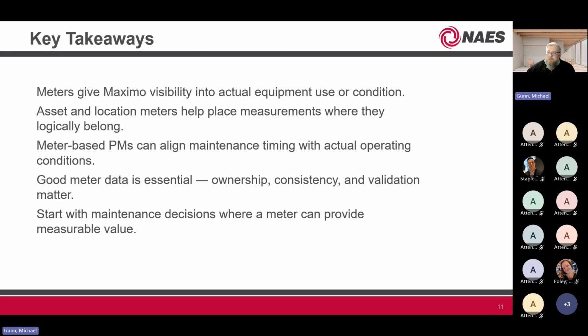Good meter data is essential - that's about ownership, consistency, and training technicians or whoever is taking readings. If it's not automatically integrated, you need to take proper readings and double check and validate the information from time to time. I don't know how many times I got calls when I was a Maximo admin saying our guys messed up this meter reading. They had access to fix it, but we just had to go back and fix it because someone saw the readings were way off. Or we triggered a 20K maintenance work order when we knew the readings were somewhere around 12K. So those indications can show when you have improper data, and you just have to go back and clean it up.